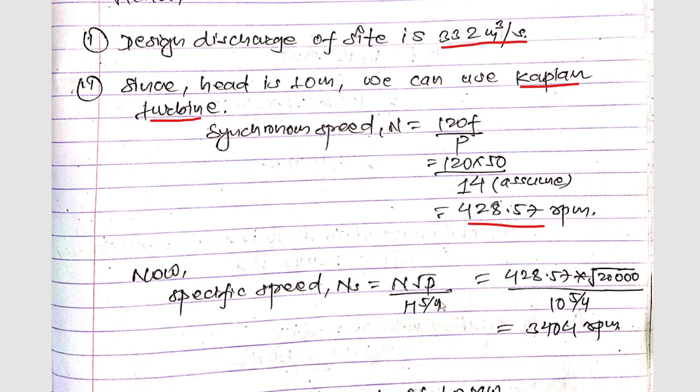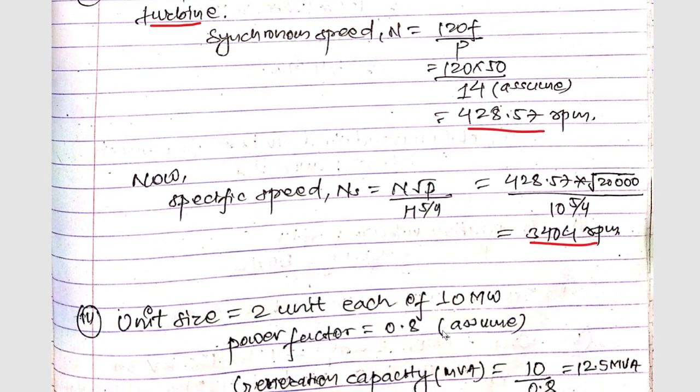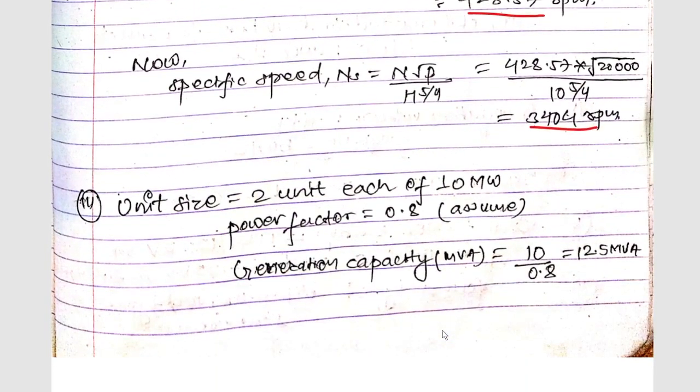The specific speed is Ns = N√P / H^5/4. With N = 428.57 and P = 20,000 kW, we calculate: 428.57 × √20,000 / 10^5/4, giving 3404 rpm.